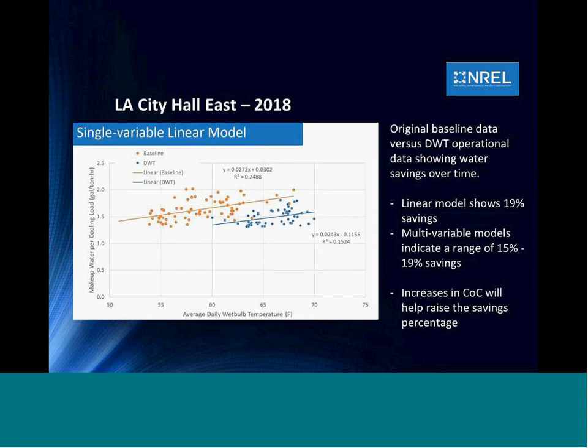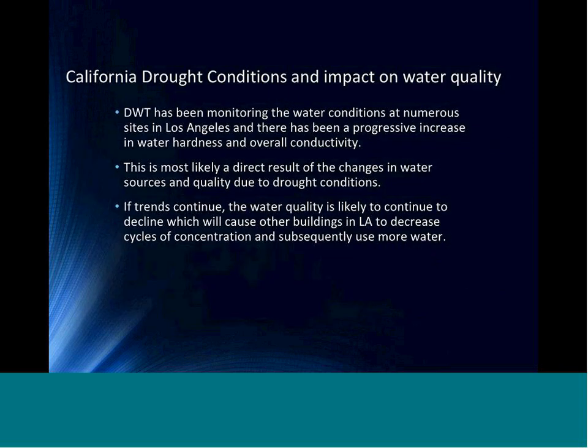So they're doing a very, very careful measurement process. NREL, we're not dictating how they do it. This is up to them. They put in several different devices for monitoring, as well as working with JCI and the City of LA. They are doing several different models that are adjusted according to the demand, the building demand, the weather, the dew point, and they're showing anywhere between 15 to 19% overall water savings for the process at this point. Next slide, please.